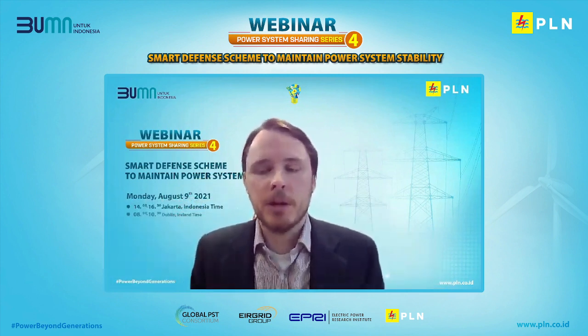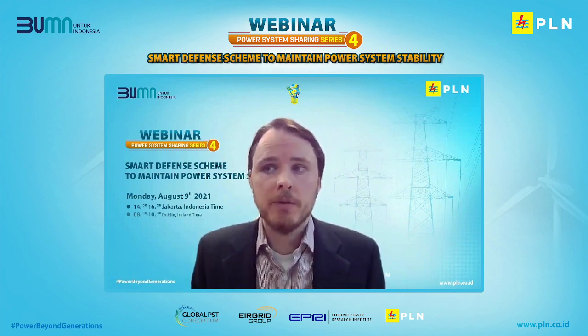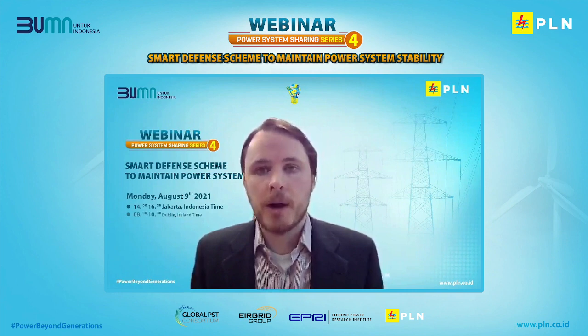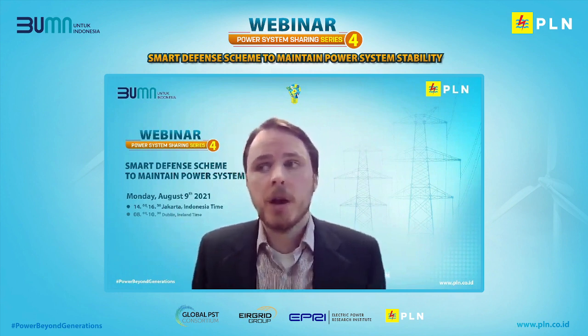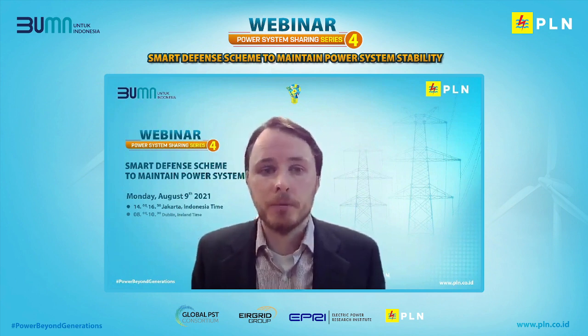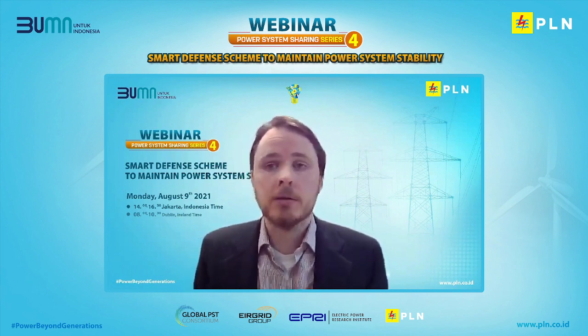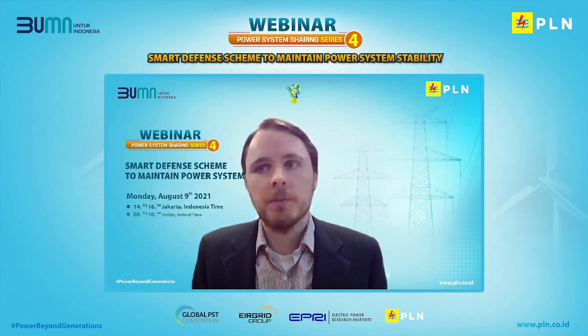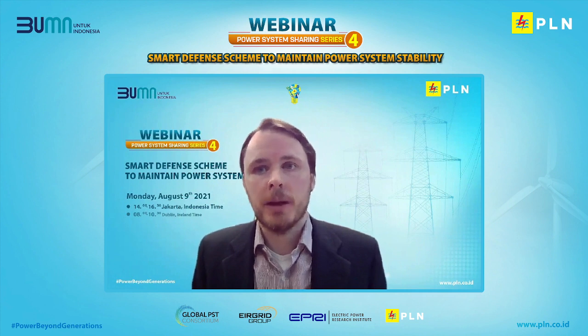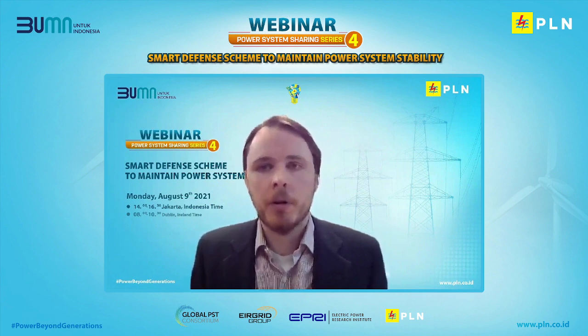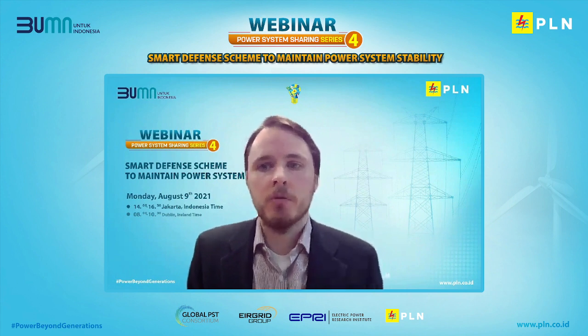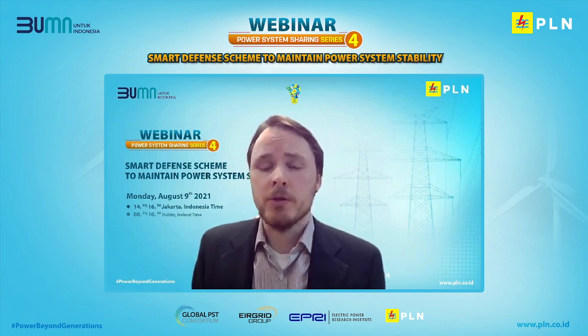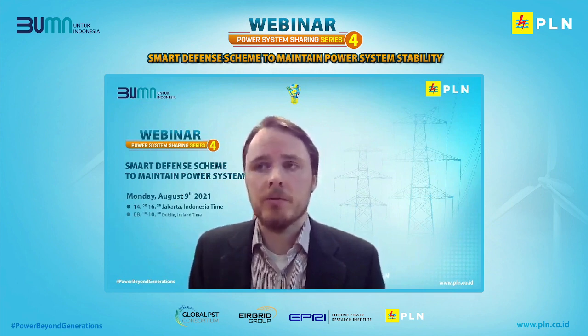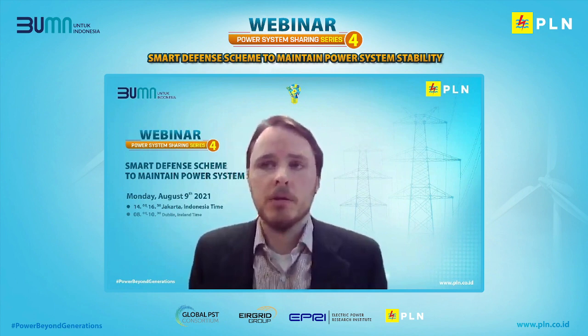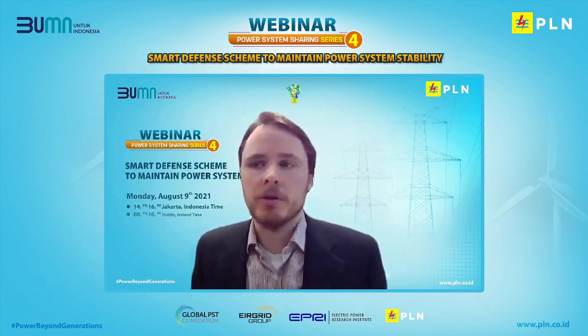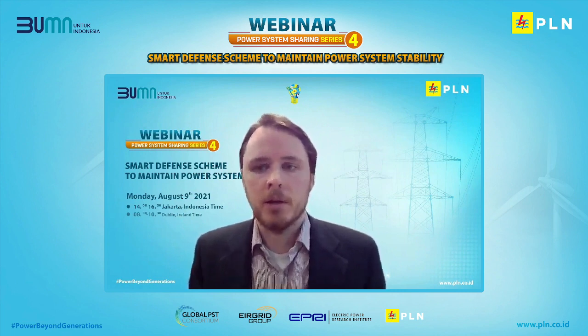In some cases, you may be able to bring a generator online, particularly if you have a hydro plant, which are capable of ramping their power output very quickly. If you have those available, or if you have pumped storage or battery banks, which can respond very quickly, it's possible to put those in place to quickly ramp up their power or absorb power and use those to mitigate the overload instead. But if you do not have those resources available, then unfortunately load shedding may be the only way to go. In some cases, you can trip generators to reduce the overload in a local area.